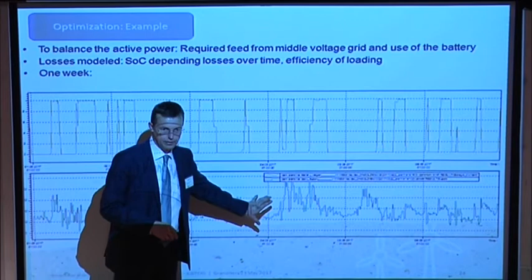And the same as shown this morning, this is all together. Here's the 0 line. Everything which is below is load, this is the active load. Here you see the charging times every time the battery is charged. The peaks over the 0 line are discharging. The photovoltaic and the rest is taken from the grid. Well, just believe me, the sum is 0. If you take everything together, the sum is 0, and that's the task of the system.